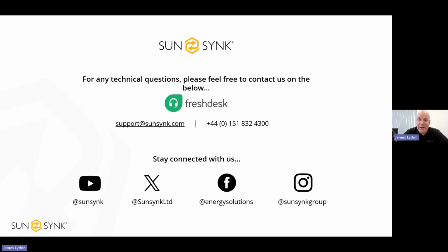If you are struggling, our telephone number is on there. That will go through to our main call center, and they will then put you where you need to go, whether it's tech support or pre-sales support. But again, what I mentioned at the beginning of the call: for installers moving from one brand to another, the installation of the inverter isn't really an issue, because essentially they're a big plug socket. It's the commissioning of it, setting up the app. So we're fully aware of that.